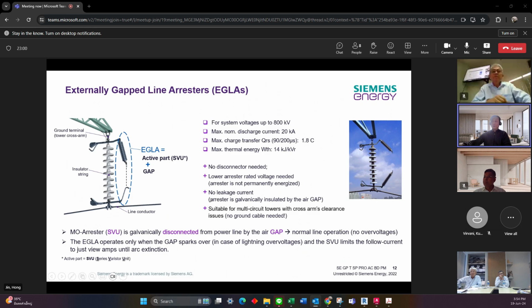And also a very important benefit is no leakage current. Therefore, in normal condition, there is no galvanic current path for leakage current. And there is also no such aging behavior on the surge arrestor itself. And this is also suitable for multi-circuit towers with cross arms, because you see it can be installed integrated on the insulator itself. It can save a lot of space. Yeah. We don't need to have installation in parallel to the insulator. We can save space on the tower.